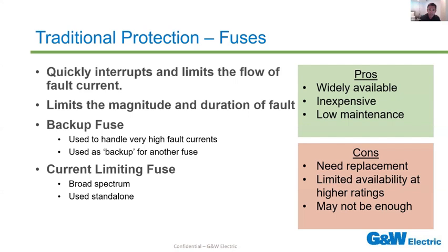The pros are that they're widely available, they're inexpensive, and they're very low maintenance. But the cons are that they need replacement every single time there's an operation, right? They're expended. They have limited availability at higher ratings. Most of these are rated under 1,000 amps of continuous current. And honestly, in a lot of situations, they just are not enough. Just like fuses, they are also limited in flexibility, constrained by their TCCs, or time current characteristics. We also call them melting curves.